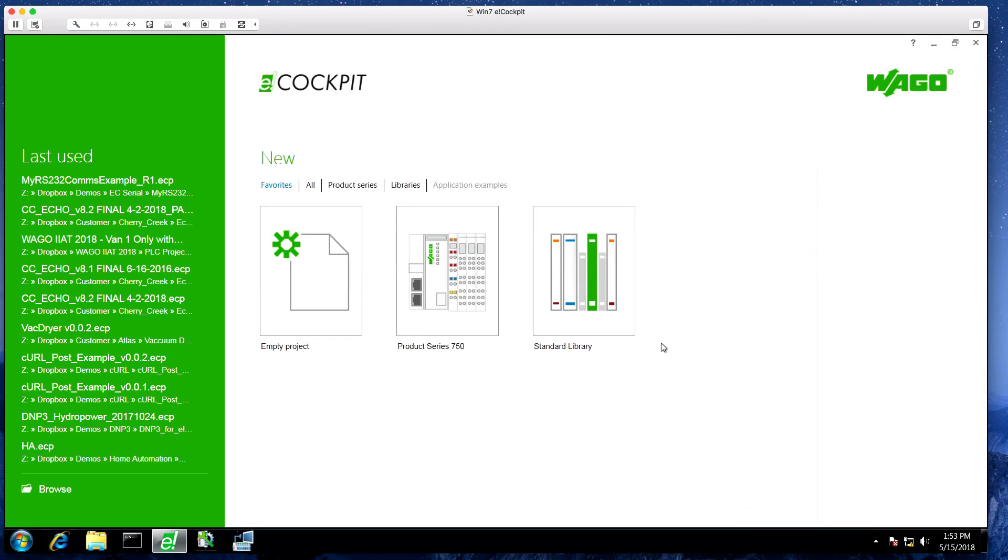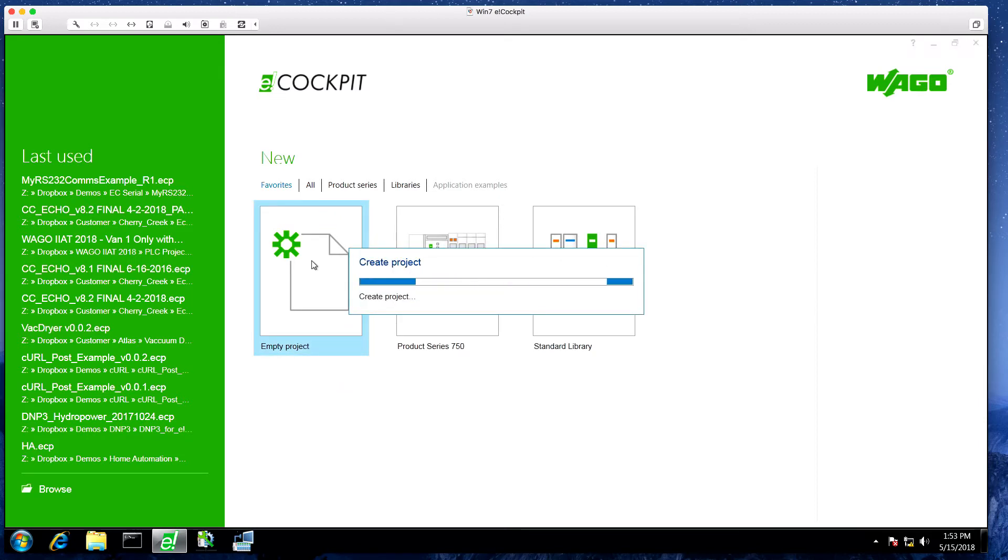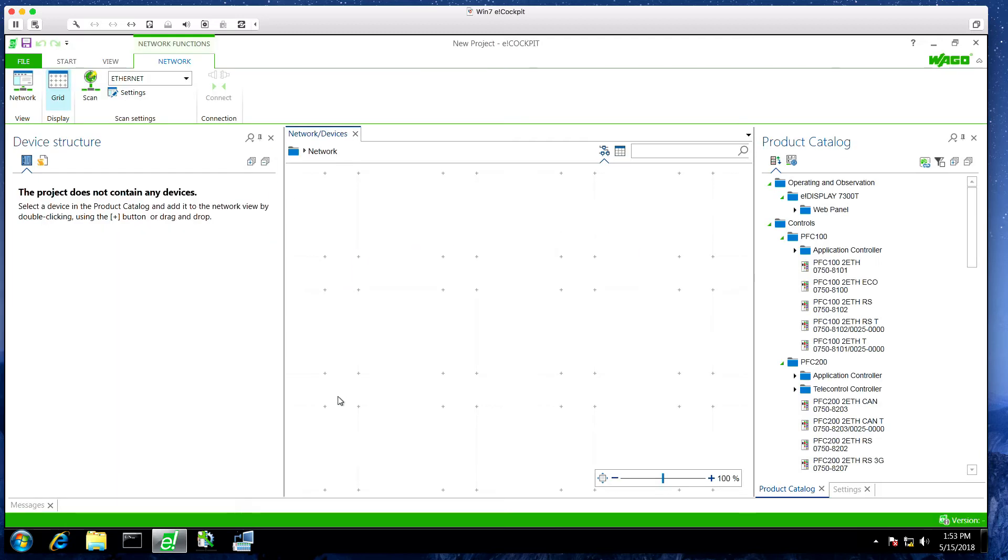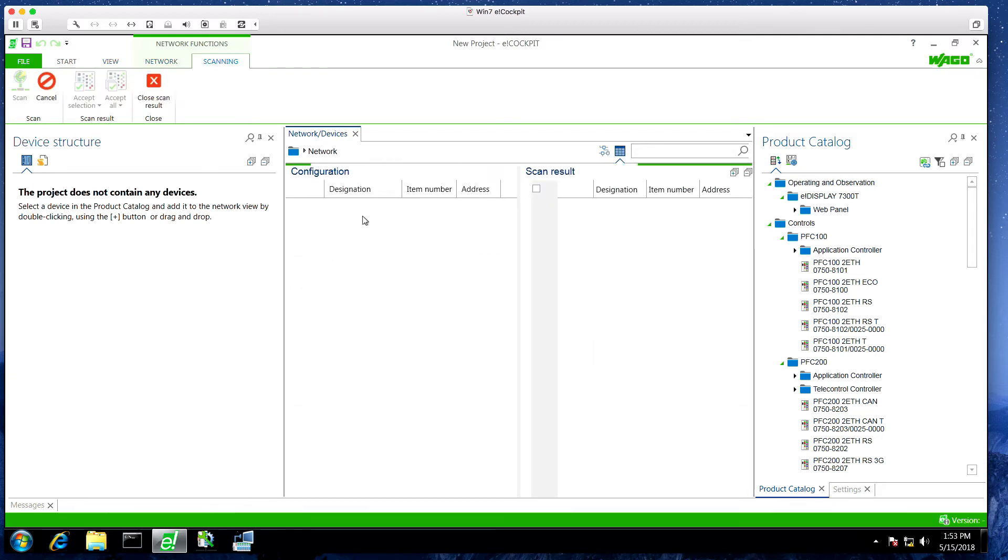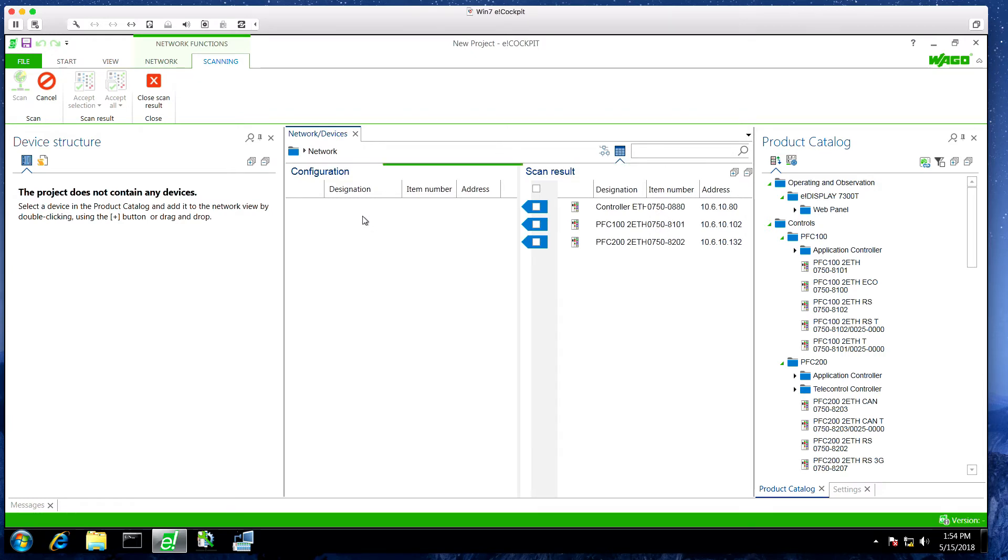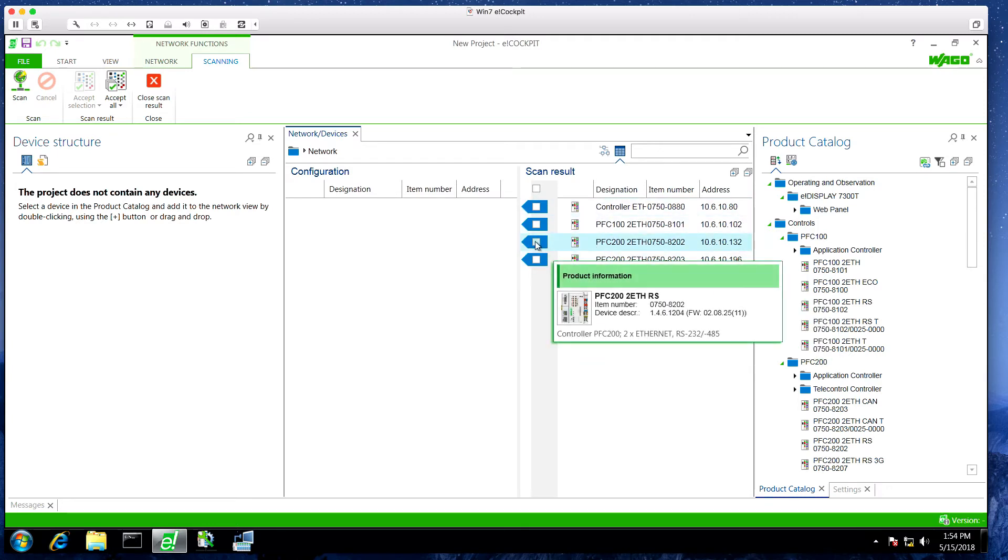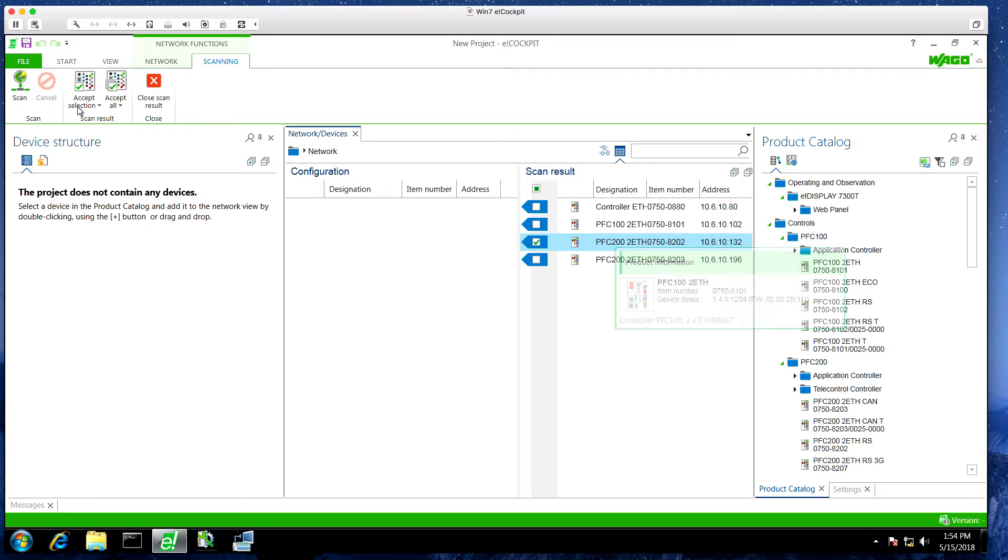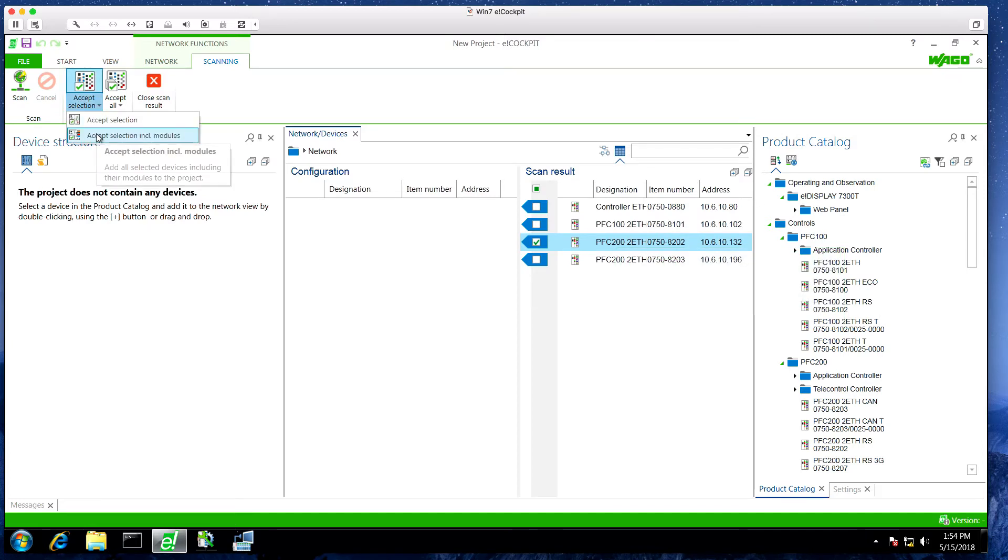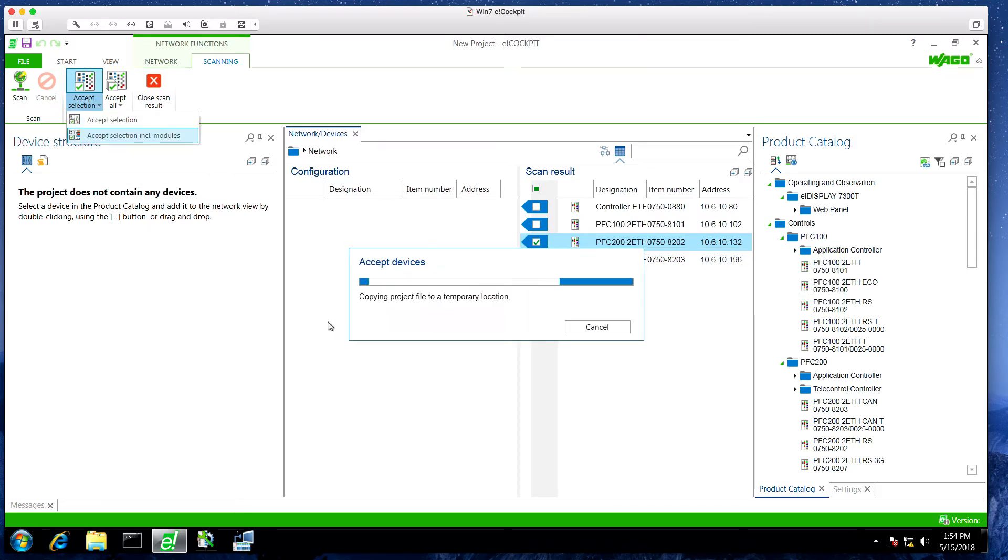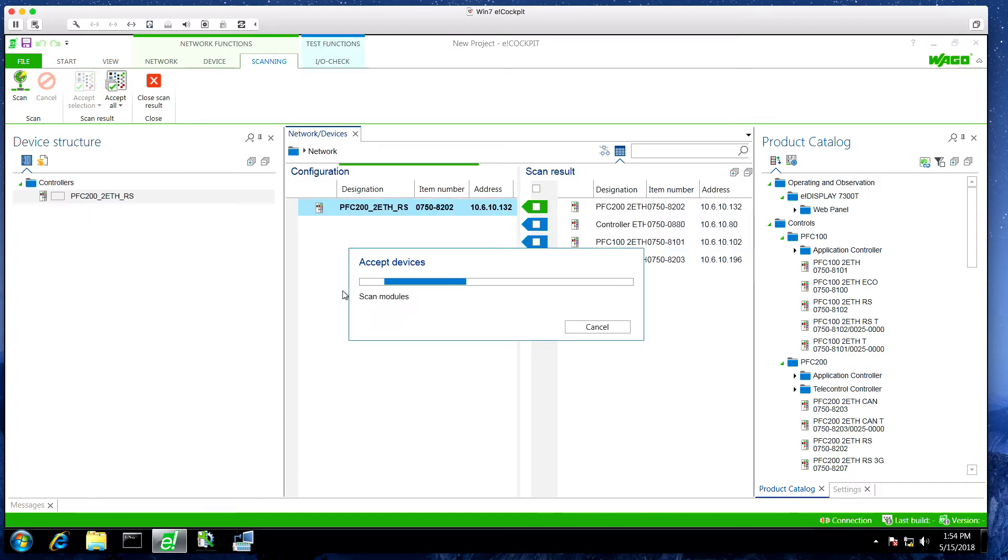For the next step, now that we have Python running in the controller, we need to create an eCockpit project that can invoke that script. So the way we'll do that is we're going to create an empty project. After this project opens, we'll add our PFC 200. We can scan our network. Now that that scan is complete, we've got all of our controllers here. I want to select this PFC 200. I'm going to accept the selection including the I/O modules and add it to the project. We won't be doing anything with the I/O, so we can just go straight into the programming window.